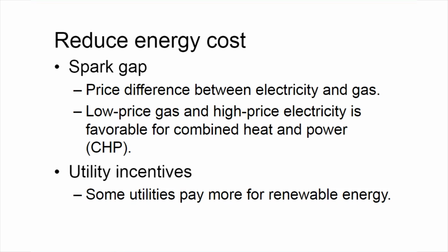Reducing the energy cost, continuing to look at that, the spark gap really has to do with whether you've got low-cost gas and high-cost electricity and whether you can take advantage of that. I had a project that had a really great gas rate, to the point that they could put $30 worth of natural gas into a combined heat and power machine and get $100 worth of electricity out of it, just based on the way their rates were set up. And so you could look at that as being essentially able to print money. And then if you have it in a combined heat and power situation or trigen situation, you can also utilize the heat, which you're basically getting for free at that point.